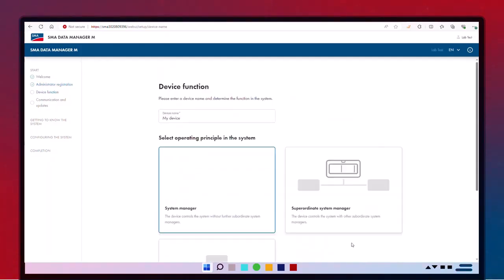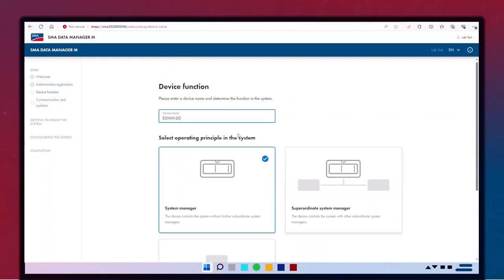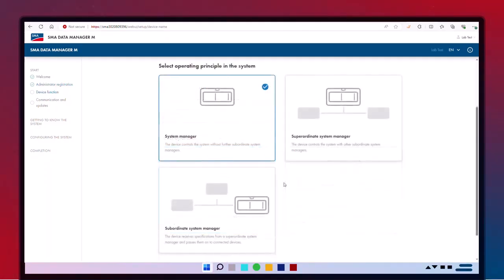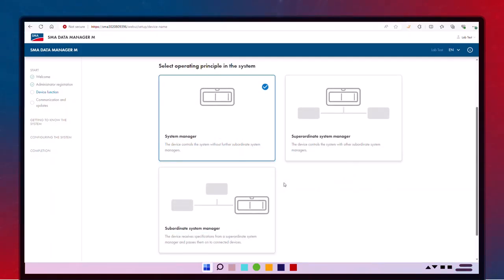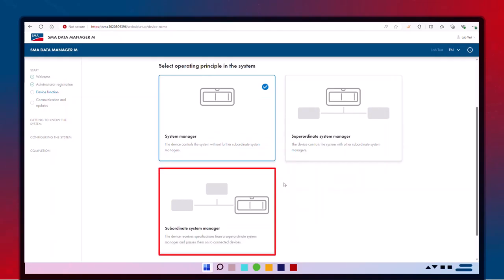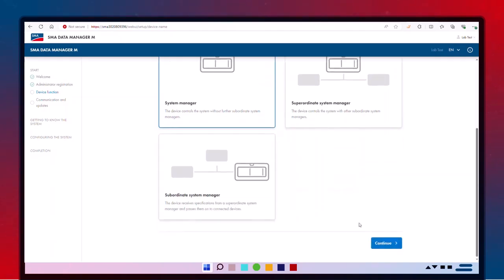Name your EDMM-20 and select its role based on your system's design. For most setups with one EDMM-20 managing up to 50 inverters, choose System Manager. For larger projects with multiple EDMMs, select Superordinate or Subordinate depending on each device's specific role within the system.